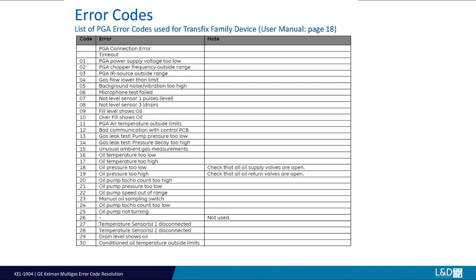When notified of the following error codes, these actions and procedures may resolve the system error code or message displayed. All the system alarm error codes are accompanied by illumination of either the blue service light that is visible on the front door of the product, or the flashing green power light as on Minitrans. Also, the service relay will be toggled to inform the customer distribution control systems or SCADA of this issue. If after the next scheduled measurement run there are no error conditions present, the system service alarm switches off. This type of alarm can occur if the condition is temporary and most probably caused by a proximity factor.